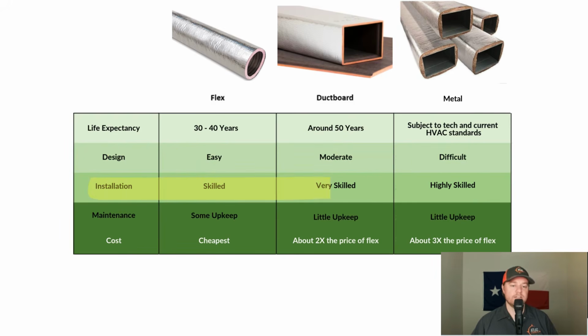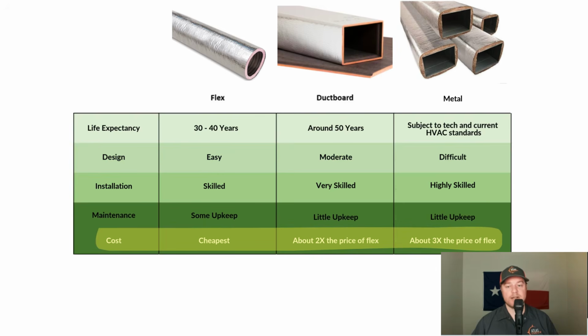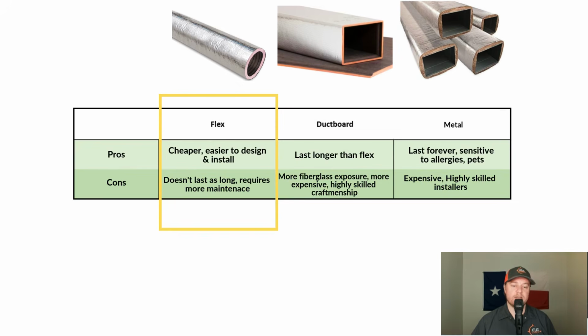We can see that the technician to install flex does need to be fairly skilled. When it comes to ductboard, they need to be very skilled, and for metal, they need to be at the top of their game. For maintenance over the years, flex is going to have some upkeep, ductboard and metal is going to have little upkeep. When it comes to cost, flex is going to be the cheapest, ductboard is going to be about double the price, and metal is about 3 times the price. So the overall pros for flex is that it's cheaper, it's easier to design and install. The cons is it doesn't last as long as the others and requires a little more upkeep.